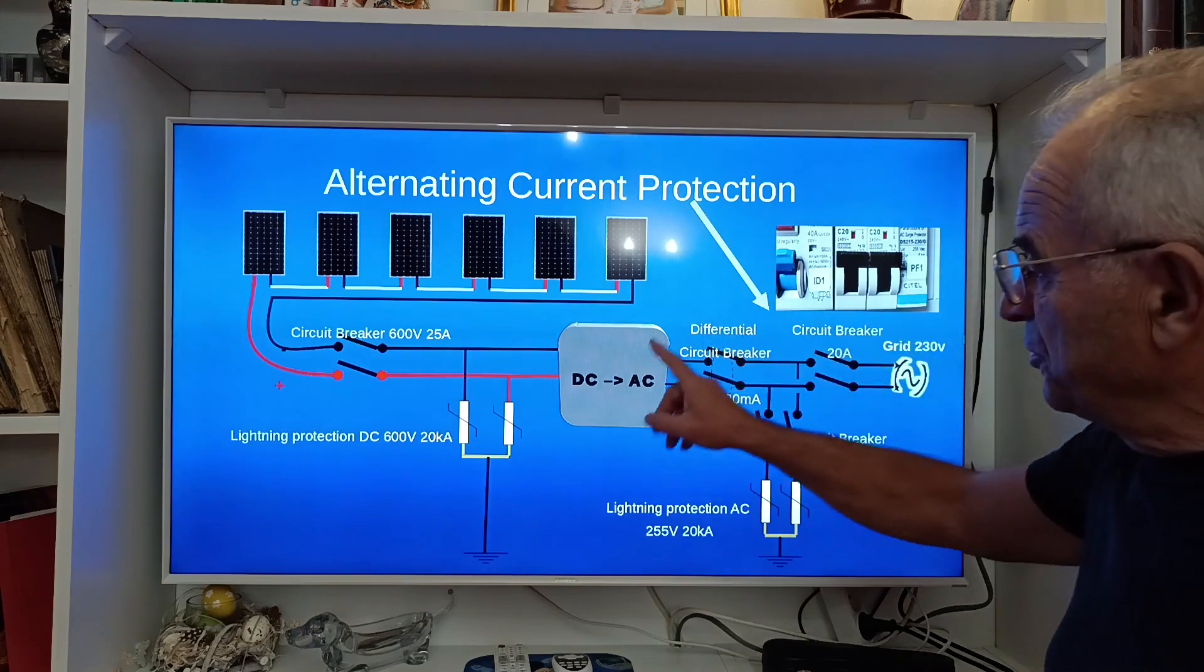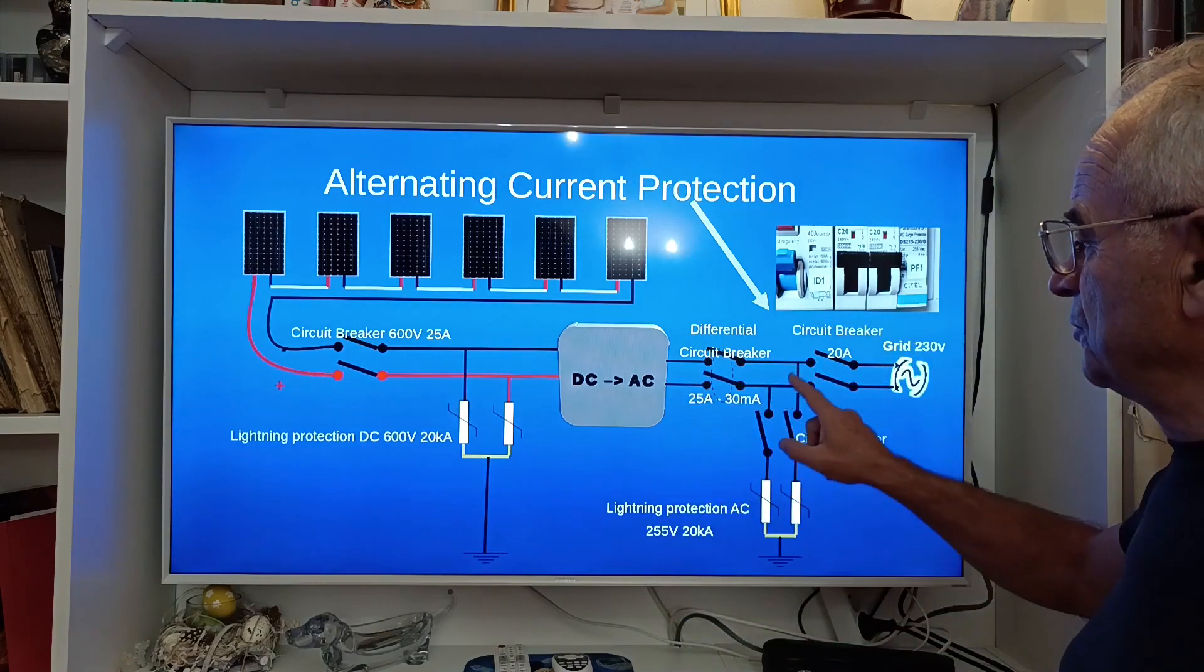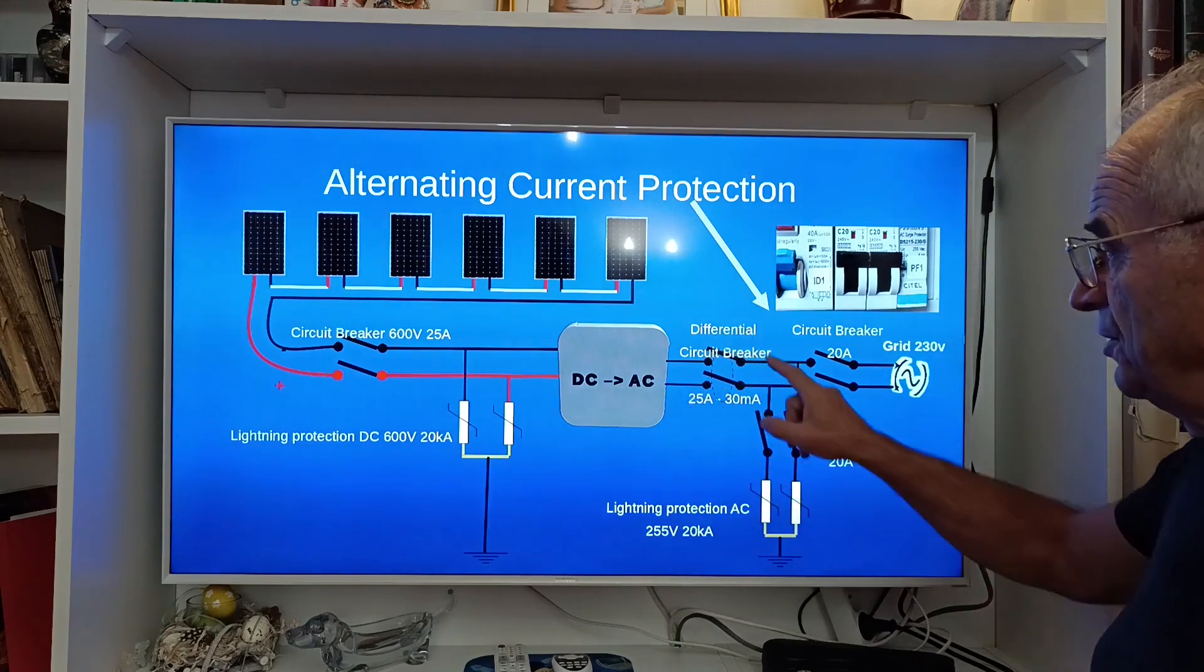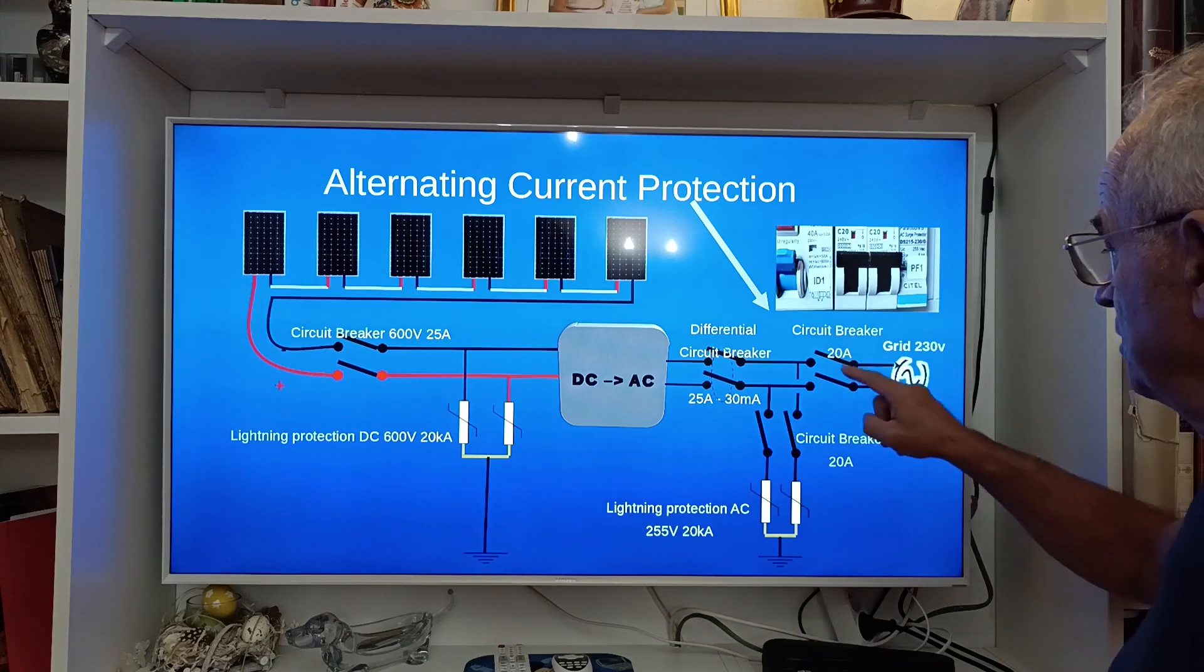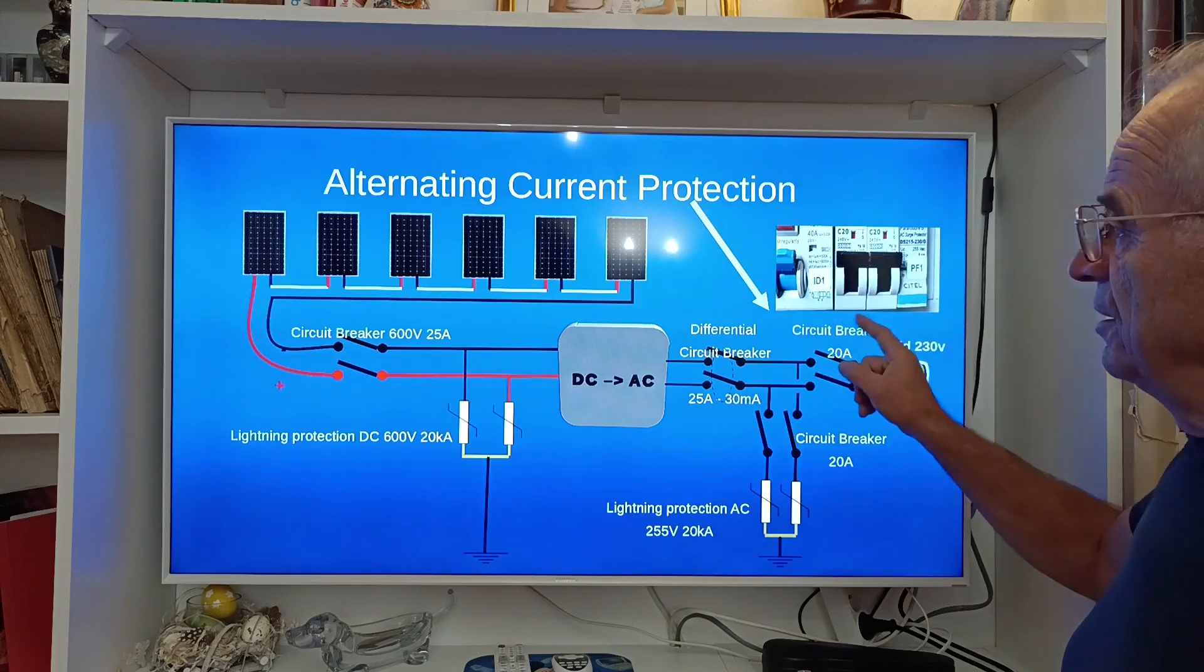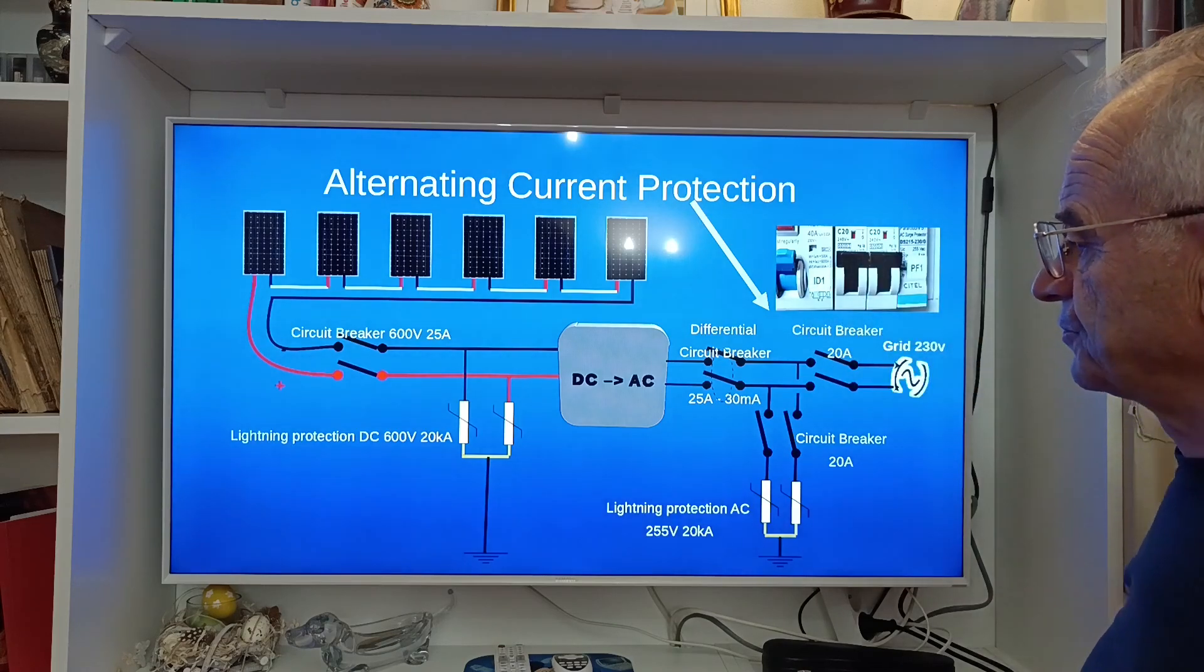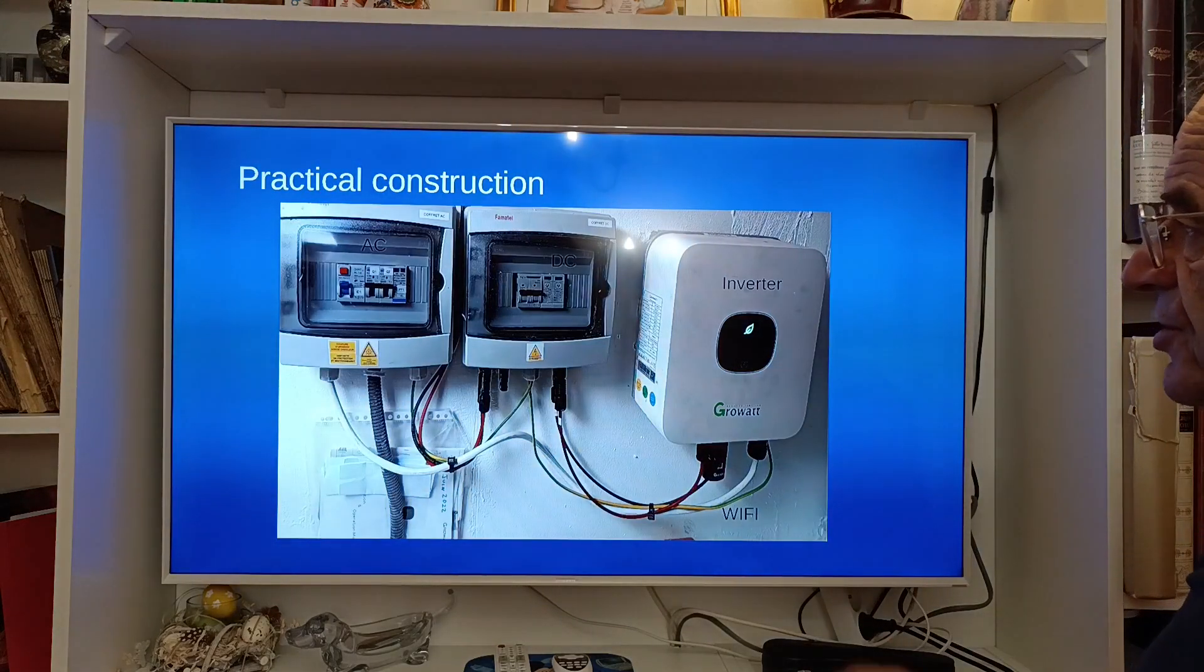At the output, on the AC output of the inverter, we have to put also a circuit breaker, a differential one, as we have in every house, a circuit breaker of 20 amps and a lightning protection on the AC side. This is the complete configuration.